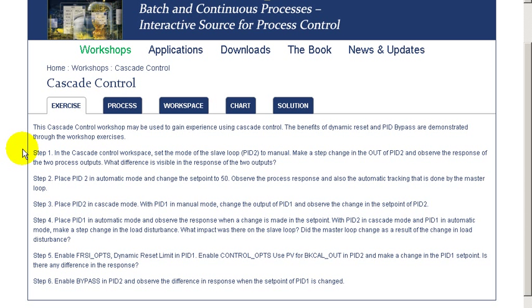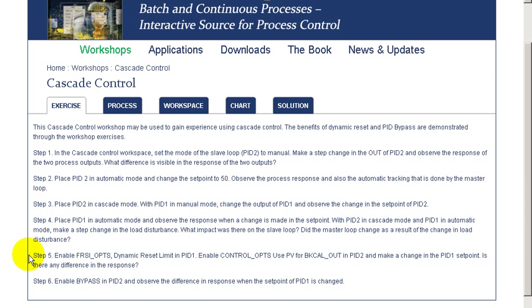In the first part of the exercise, we'll identify the process dynamics and then look at the slave as well as the master response in automatic mode to a setpoint change. We will then introduce a disturbance into our process and examine the behavior of Cascade Control when a disturbance is impacting our slave loop. We will then look at the techniques required to enable dynamic reset on our PID and examine its behavior in terms of setpoint change, comparing it to Cascade without dynamic reset. Last, we will examine Cascade Control with bypass enabled on our slave loop.